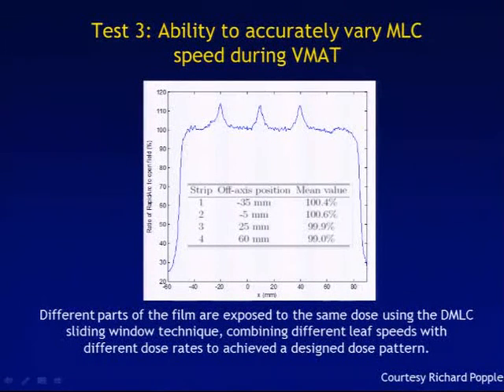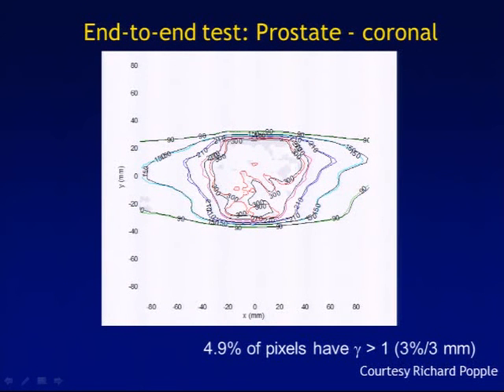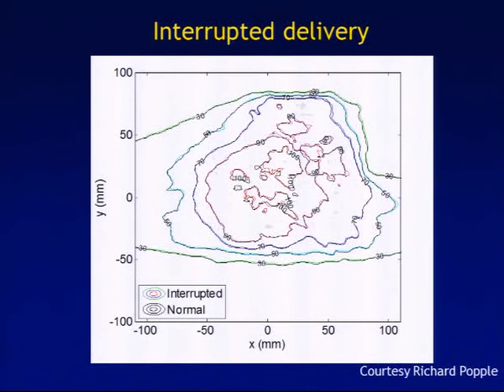The third test is testing the ability to accurately vary the multi-leaf collimator speed during VMAT. Different parts of the film are exposed to the same dose using the DMLC sliding window technique, combining different leaf speeds with different dose rates to achieve a designed dose pattern, and again showing uniformity of the mean values. In the end, what matters is being able to do end-to-end tests and verifying complete delivery accuracy. A coronal view of a prostate verification shows close match between planned and delivered isodose distributions. Another important test is the impact of interrupting the delivery — cutting off the beam during an arc multiple times to see if it impacts the accuracy of the delivered dose.